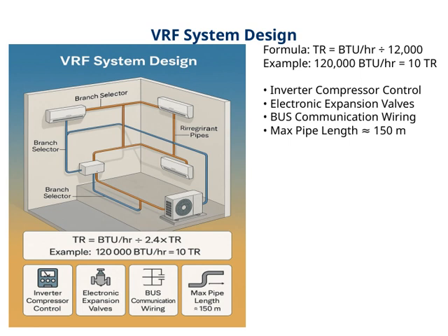This technology allows the compressor to operate at variable speeds, which means better energy efficiency and more precise temperature control. Another important component is the electronic expansion valves. These valves adjust refrigerant flow dynamically, optimizing system performance and ensuring consistent comfort.